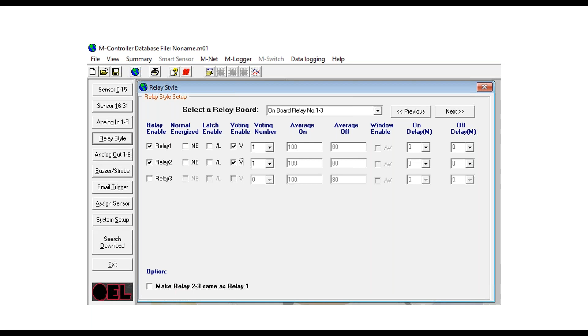I'll touch base on this too, where on the M controller, for example, there are 3 relays. Let's say we've got 2 floors and, say, 8 sensors on each floor, and you've got 2 dedicated exhaust fans for each floor. You can latch the sensors on floor 1 to relay 1, and latch all the sensors on floor 2 to relay 2. So only when any one of those sensors goes into alarm will they turn on the fans on that particular floor. You don't have to have both floors coming back to one relay and everything turns on.